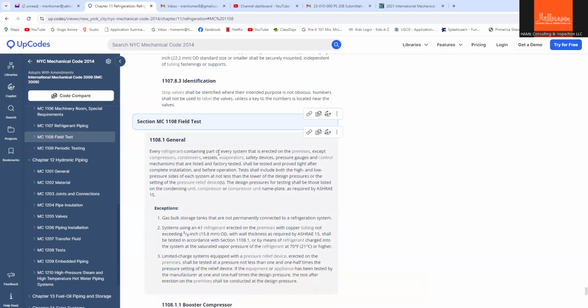So the refrigerant-containing parts that are erected in the premises shall be tested to prove tight after complete installation and before operation. The test shall include the high and low pressure sides of the system at not less than the lower of the design pressure or the setting of the pressure relief valve. The design pressure for testing shall be those listed on the condensing unit compressor unit nameplate. So that's your reference point where you're going to find your pressure to be used for the test. So it's the nameplate of the condensing unit.